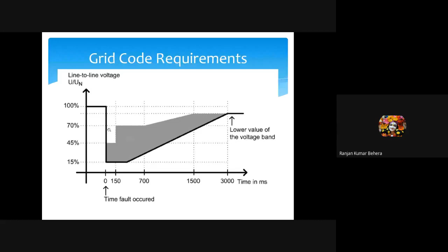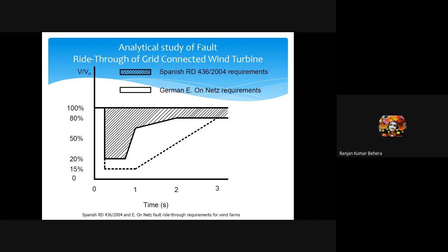And this then slowly brings it to nearly the normal stage. Here we have simulated this converter for the Spanish grid code. You can see that the Spanish grid code is around 20 percent of the voltage drop, and the Germany grid code is around 15%. These two grid codes we applied to this converter system, where the grid voltage dropped to 15%, and from the 15% again this profile was applied, and accordingly you can see here.